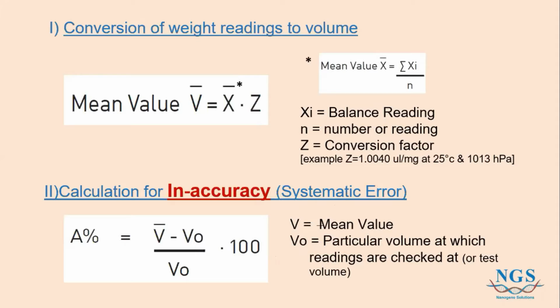All right, so let's learn how to calculate inaccuracy. Inaccuracy is a percentage value. You use the mean value that you've calculated above and subtract the particular volume at which the readings are checked, V0. For example, if you're using the maximum value, you subtract the maximum volume you're checking at, which would be 200 microliters. You divide it by, again, 200 microliters, times 100 to make it into a percentage. With that, you'll get your inaccuracy value.